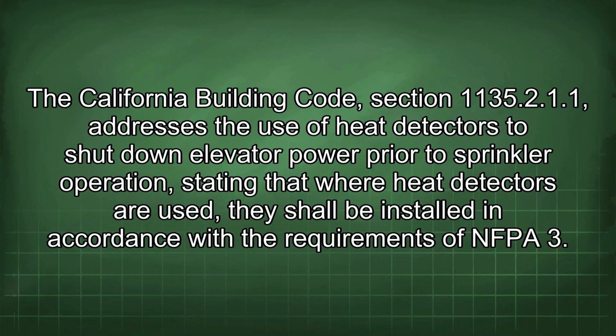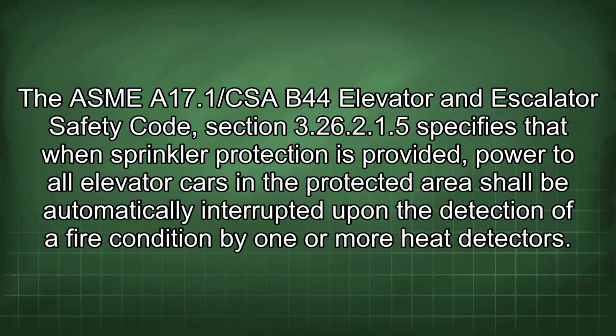California Building Code, Section 1135.2.1.1, addresses the use of heat detectors to shut down elevator power prior to sprinkler operation, stating that where heat detectors are used, they shall be installed in accordance with the requirements of NFPA 72. The ASME A17.1/CSA B44 Elevator and Escalator Safety Code, Section 3.26.2.1.5 specifies that when sprinkler protection is provided, power to all elevator cars in the protected area shall be automatically interrupted upon the detection of a fire condition by one or more heat detectors.